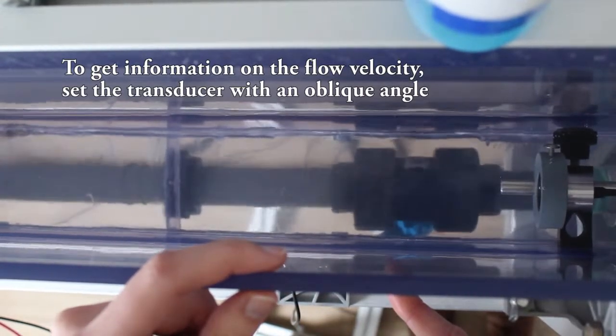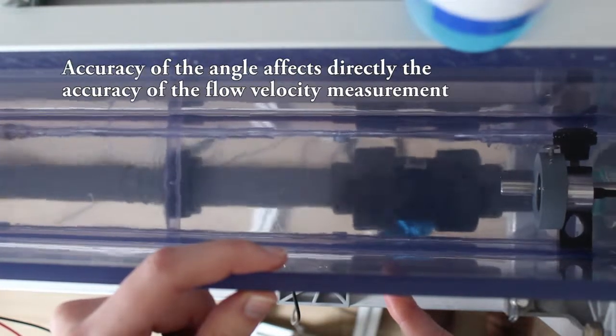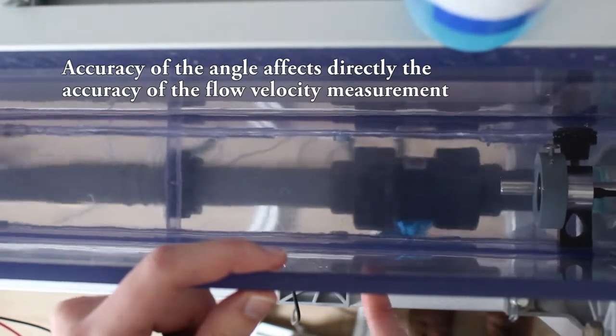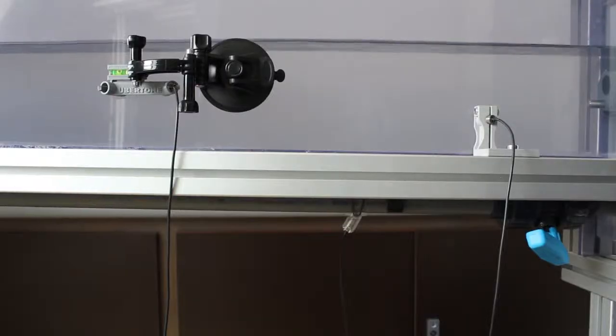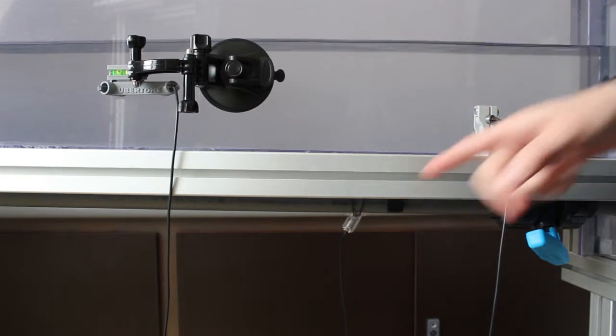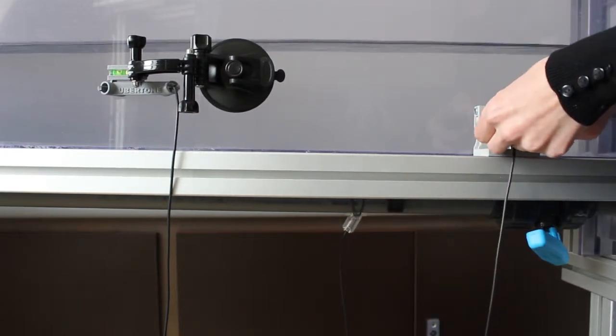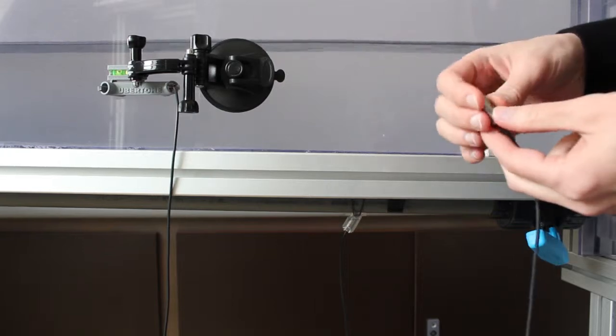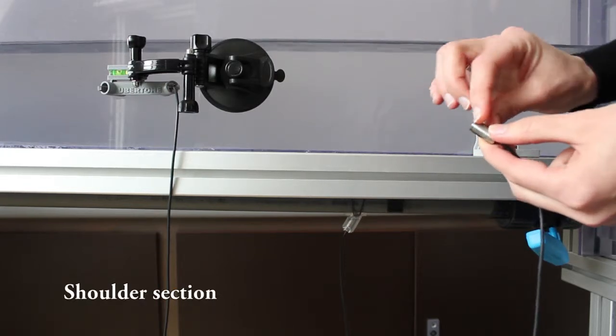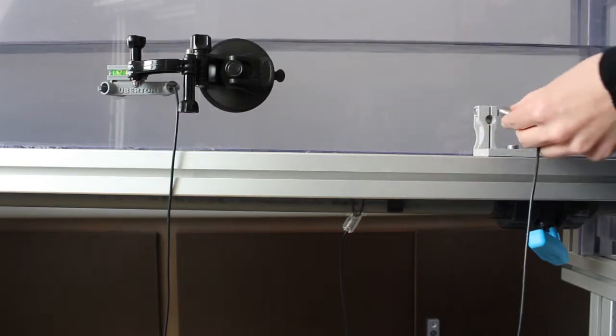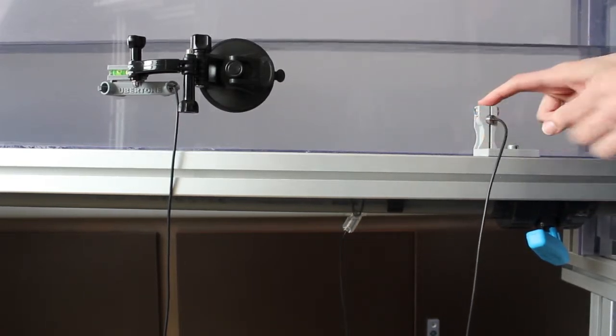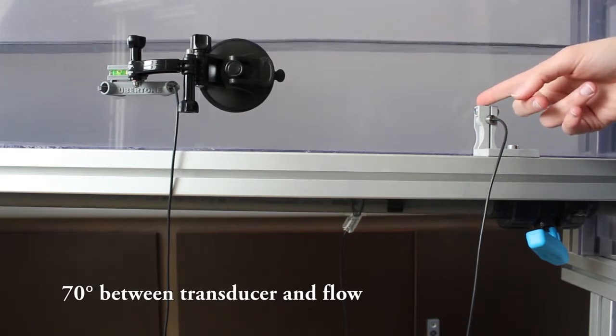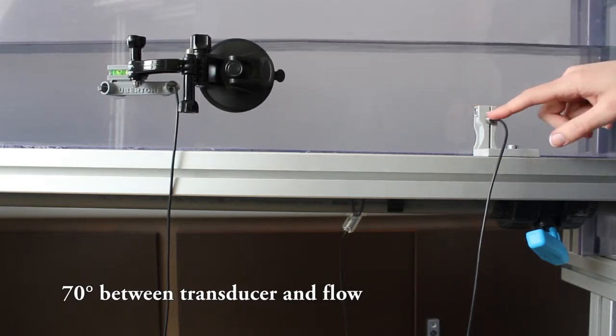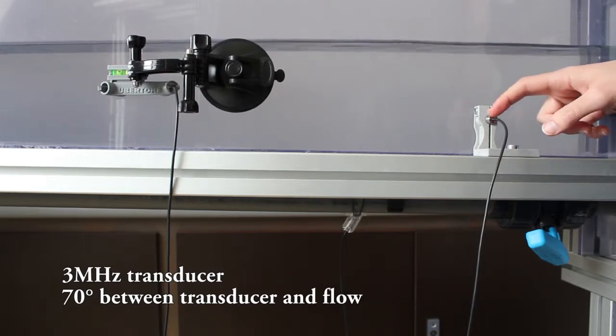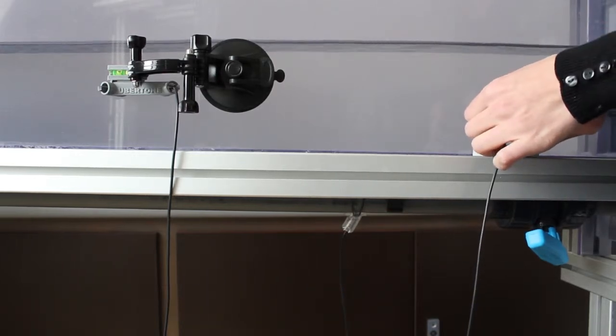Again, the transducer holder is necessary to obtain a precise measurement, as the angle affects directly the precision of your measurement. If you don't have any holder, here are 3 examples. If you want to design your own holders, note that our transducers have a shoulder section here that helps designing the holder. This first holder ensures a 70-degree angle between the transducer axis and the flow.